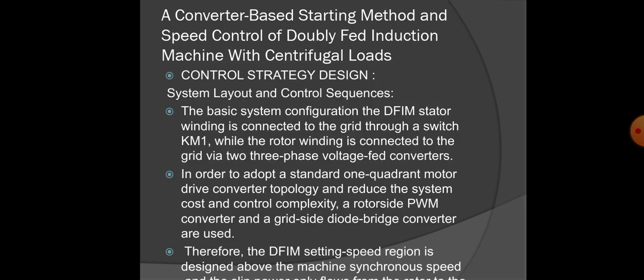And the control strategy design, the system layout and control sequences. The basic system configuration of the double fed induction machine: the stator winding is connected to the grid through a switch KM1, while the rotor winding is connected to the grid via a 3-phase voltage fed converter. In order to adopt the standard one-quadrant motor drive converter topology and reduce the system cost and control complexity, a rotor side PWM converter and a grid side diode bridge converter are used.